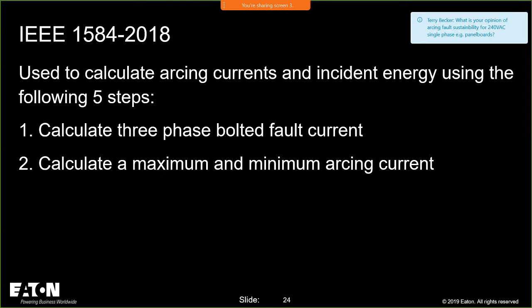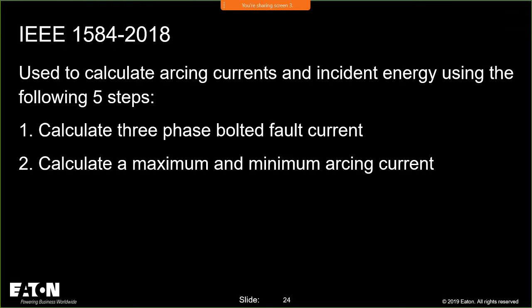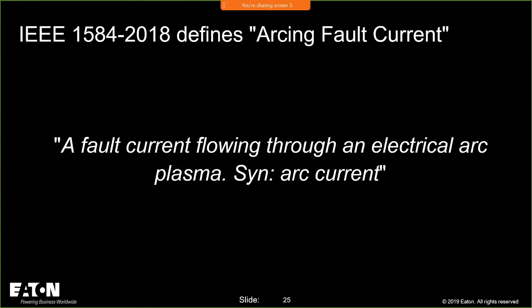So calculating the three-phase bolted fault is critical, and that's what we did on Monday. That's what I love about this program today: if you think about this week, Monday we talked short circuit currents. Tuesday we talked about selective coordination. Wednesday we talked about ground fault circuit interrupters and shock protection. We took a little detour into residential AFCIs on Thursday, and now we're pulling it all together and talking about safe work practices and understanding the hazards, and all of the stuff that we talked about this week is pertinent. Calculate maximum and minimum arcing currents. We use IEEE 1584 to do that.